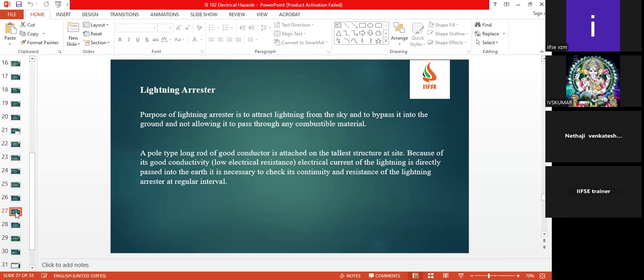So basically, these are pole type, and a long rod of a good conductor is attached on the tallest structure at the site. Because of its good conductivity and low electrical resistance, the electrical current of the lightning is directly passed into the earth. It is necessary to check its continuity and also the resistance of the lightning arrestor at regular intervals. It will be kept at the tallest building in your facility so that it will have a nice coverage, based on the different makes and different conditions.